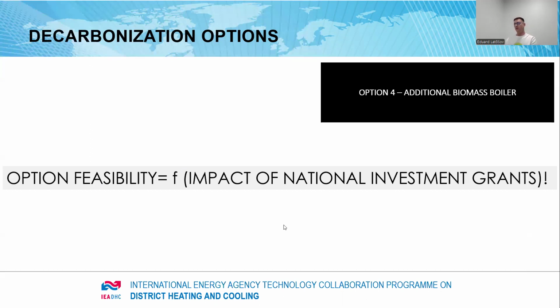But at the end, option feasibility has a strong impact from national investment grants. We had grants for heat storages and for heat pumps, and that's why we selected the option with heat storage plus heat pump for Igala. Without those subsidies, I think option 4, the additional biomass boiler, would be priority number 1. So grants have a significant impact on the solutions chosen.